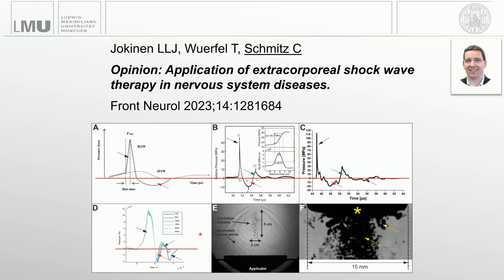To make a very long story short, the key difference between focused shockwaves and radial shockwaves is not the physics of the shockwave itself — they differ quantitatively, but not qualitatively. They both produce cavitation fields due to the negative pressure. The energy usable for treating patients with a focused shockwave device is at a distance from the applicator, whereas for radial shockwaves the energy is close to the applicator. So radial is good for superficial indications, and focused is good for deep indications.